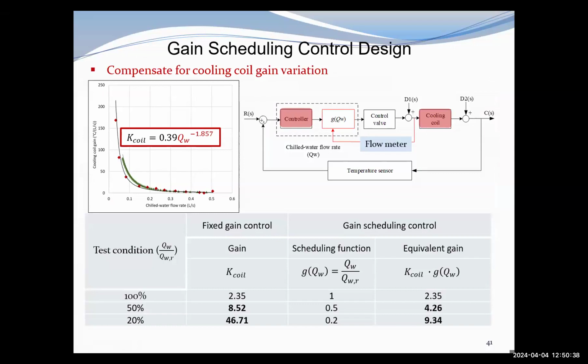And that's for the fan speed control. As for the cooling coil valve control, we also designed the gain scheduling controller to compensate for the cooling coil gain variation. So this is our cooling coil gain variation with the chilled water flow rate. If we want to design the scheduling function to entirely compensate this nonlinearity, the scheduling function will be very complicated, and also this is beyond the system's capacity. And then finally, we design the scheduling function.